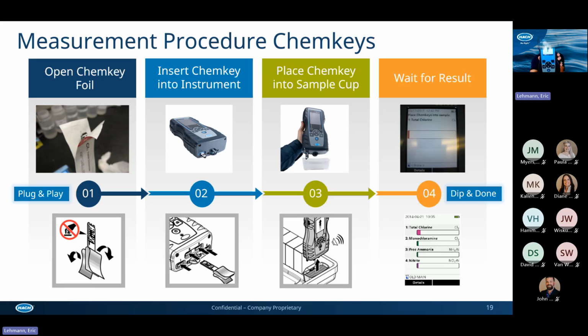Now it's telling me to take the instrument out of the sample, and it's already started its testing. So now it's going to count down on all 3 parameters simultaneously. It just happens that it takes about 7 minutes for the alkalinity test, so we're going to be waiting a total of 7 minutes before we get our results. You can tell it's a really easy way to run parameters without having to deal with any sort of reagents or chemistries. Everything's built into those chem keys.